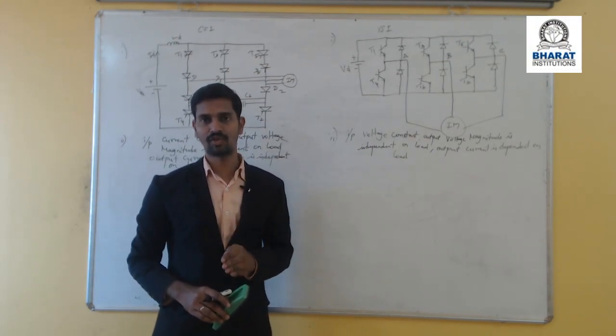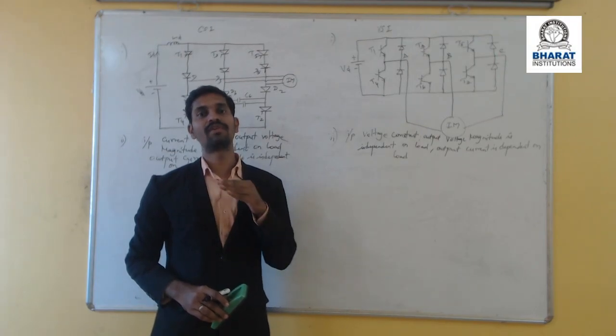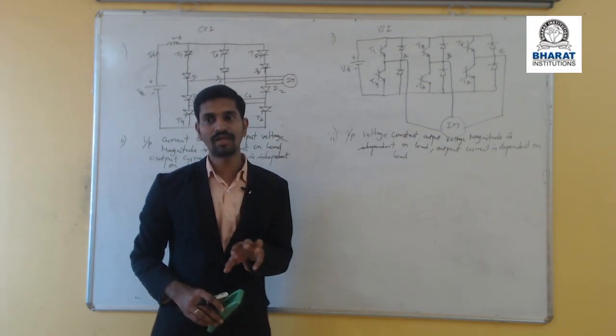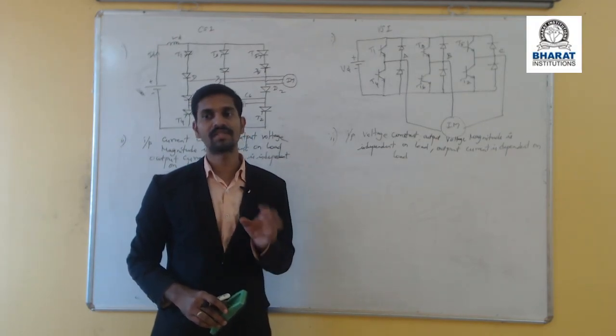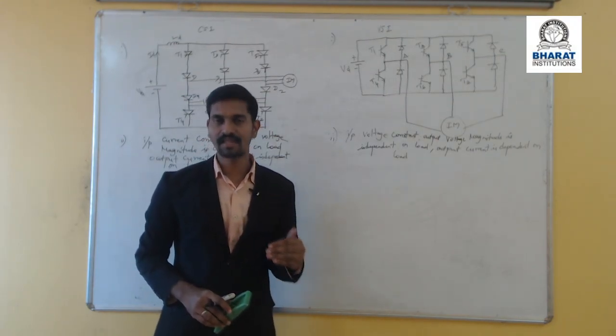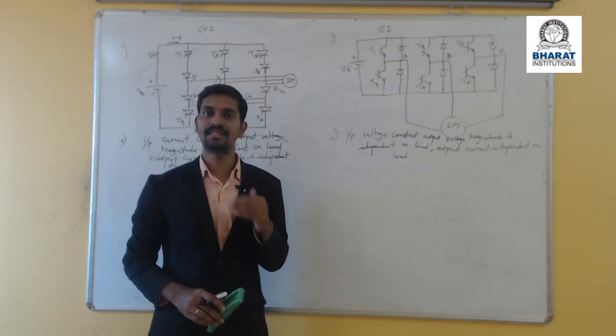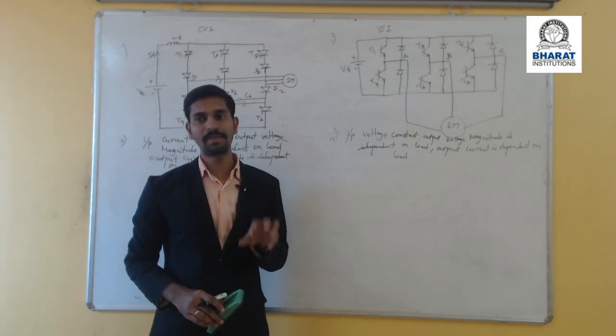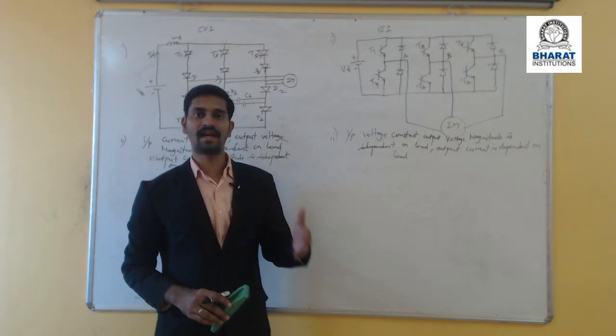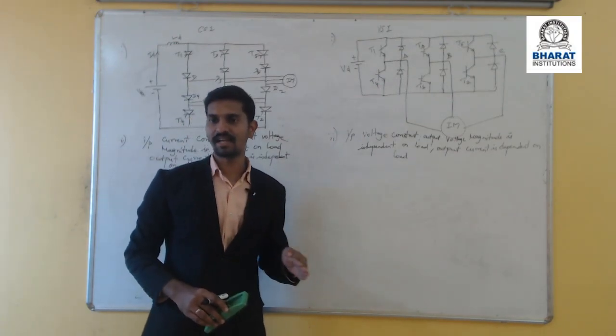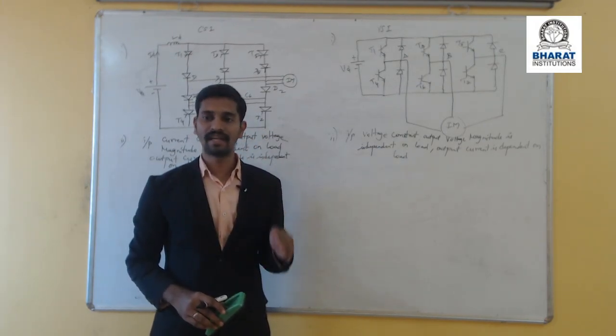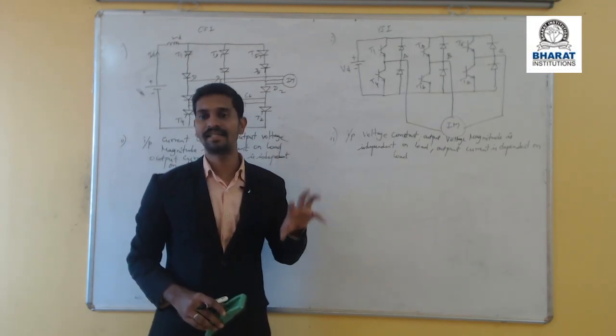With respect to the stator side control, we will vary the frequency as well as the stator voltages using voltage source inverters, current source inverters, or cycloconverters. These converters — VSI, CSI, and cycloconverters — achieve variable frequency as well as variable stator voltage, because varying the stator voltage and frequency gives us speed control of the induction motor with respect to the stator side.